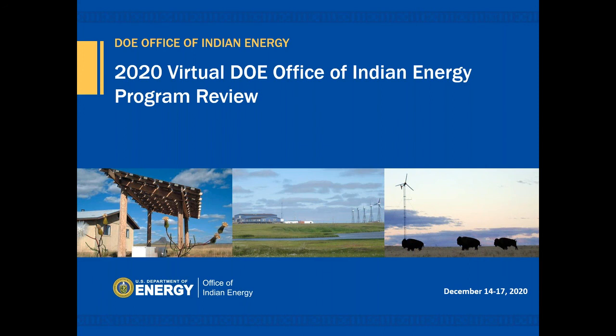In 2004 the cogen and microgrid were constructed, but we still didn't have any backup systems. So from 2004 until 2012, we averaged 5 or 6 power interruptions per year, because anytime the gas engines would shut down, we would have to transition onto PG&E to get back up and running. Every time we went from island operation back to parallel and then back to island, we would have a brief power outage. In 2012, we brought the UPS system with 4 megawatts of diesel engine backup online, and since then we've had a single outage.